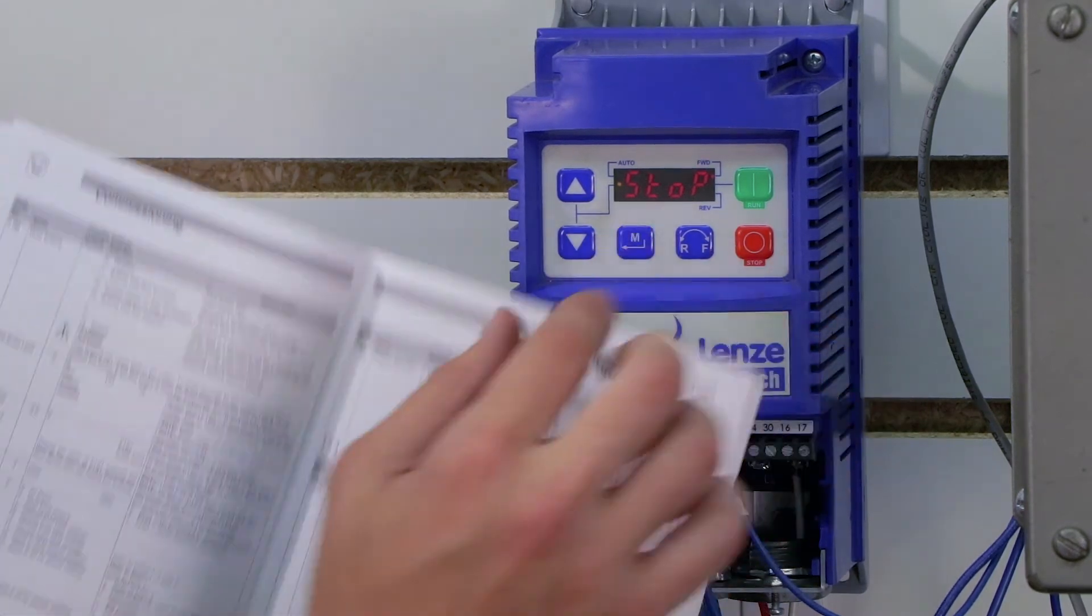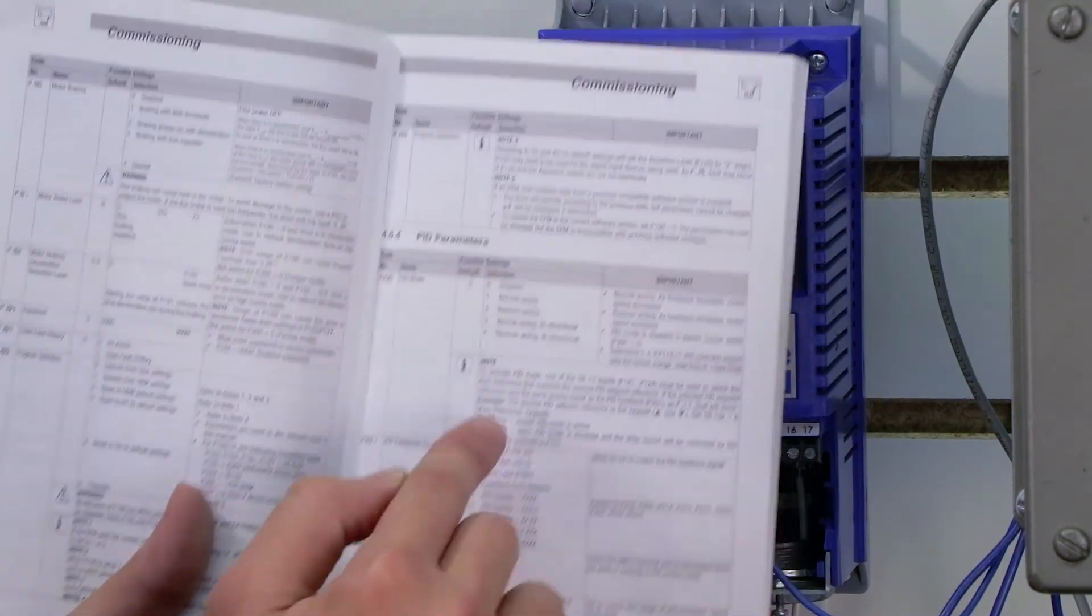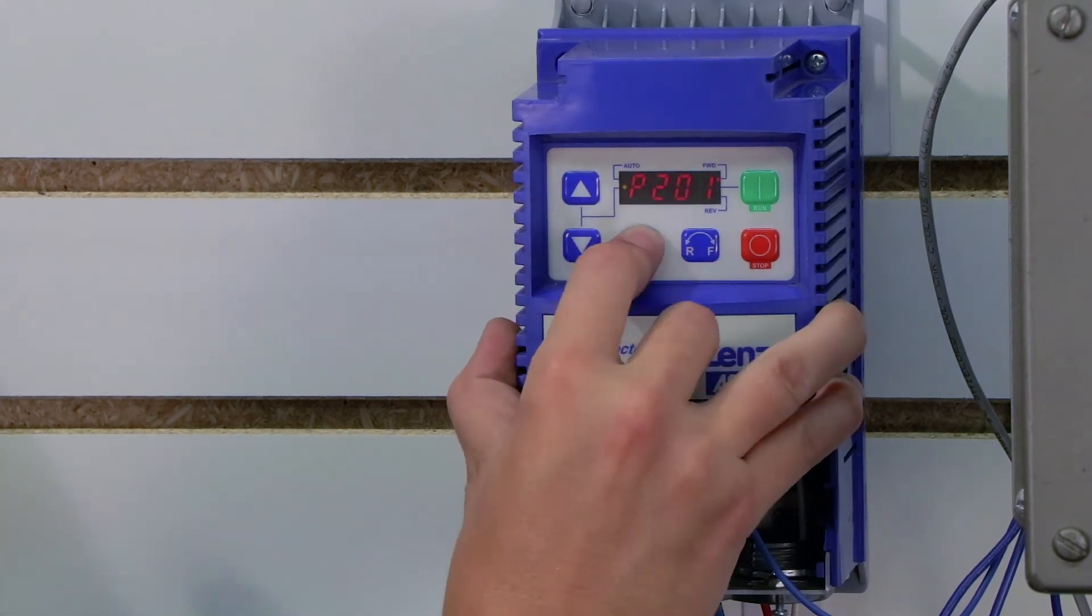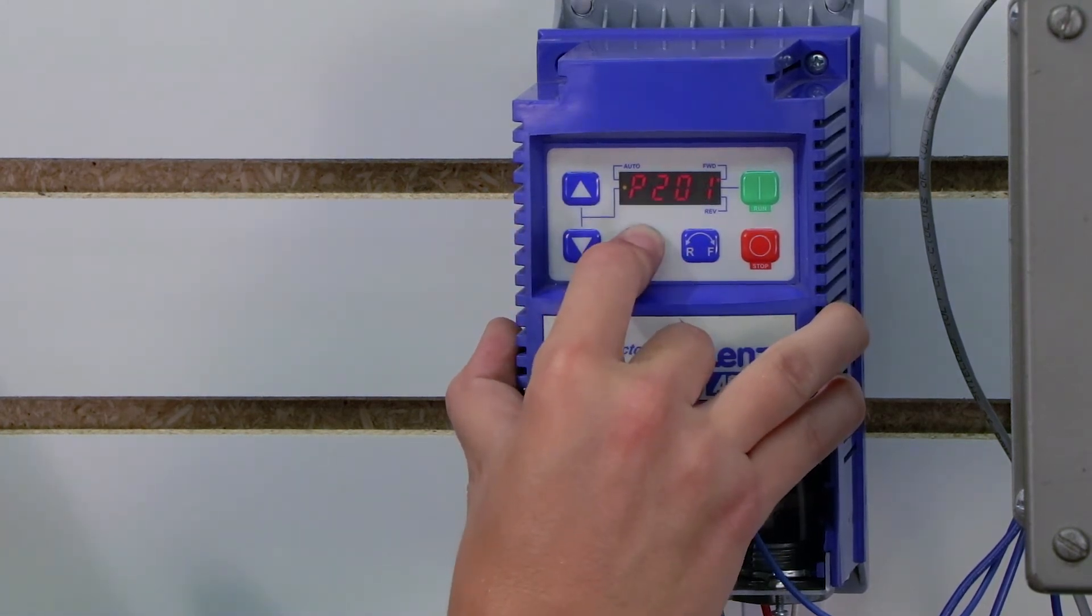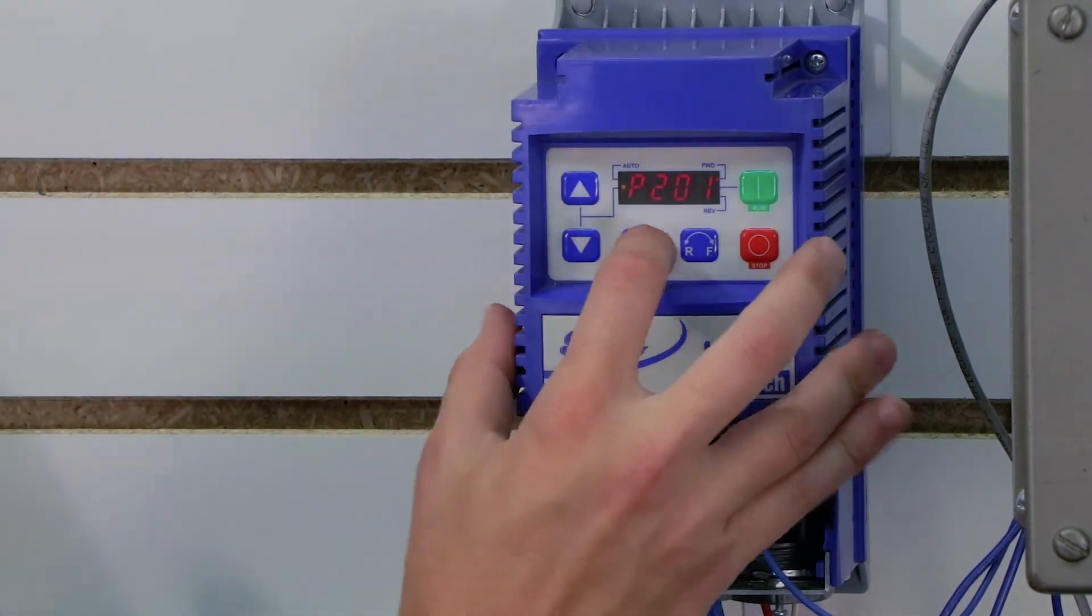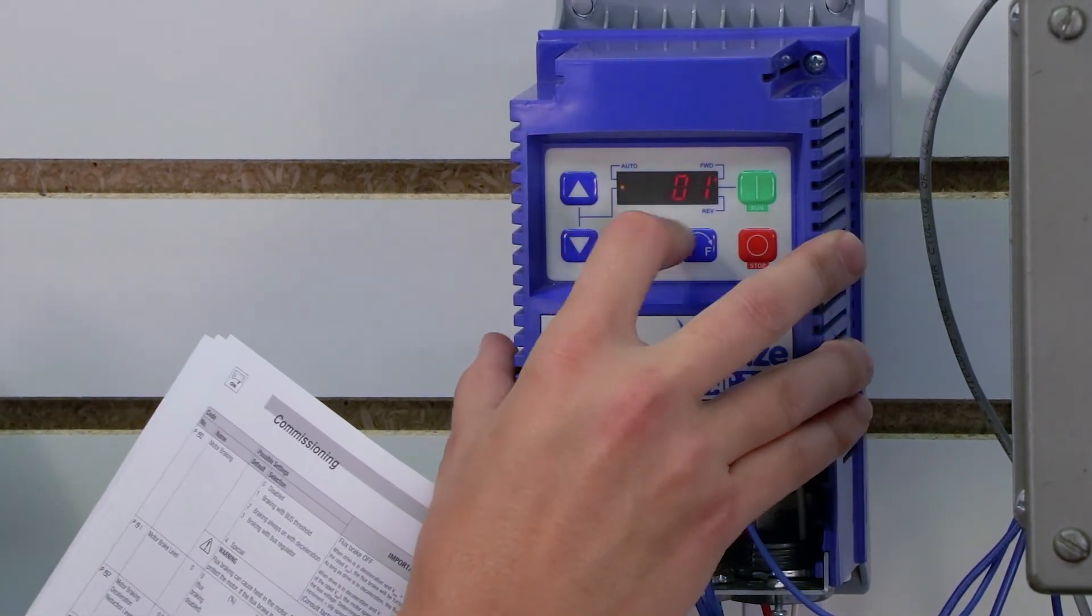My next parameter I need to set is actually parameter 201. That's my feedback source. And that's my signal that my actual water level is coming from. In my case, like I said, I'm using a speed pot. So I'm going to use this 0 to 10 volt DC. But you want to select whatever your sensor is set up for. And again, I press 201 and I set 1, which is 0 to 10 volts DC.